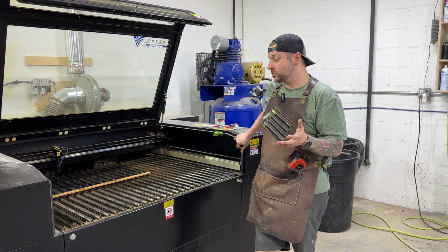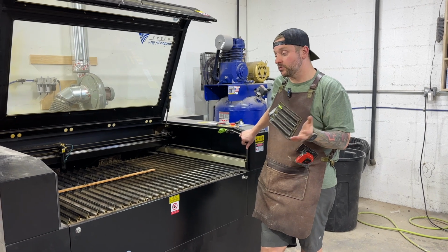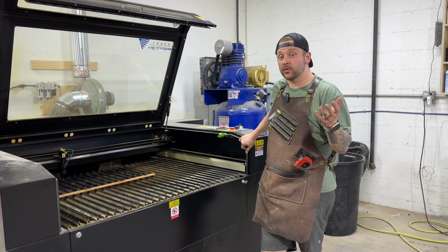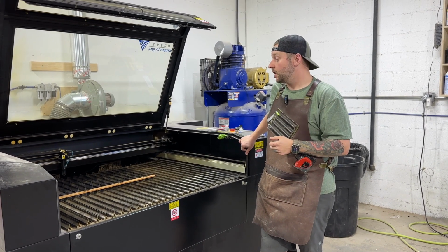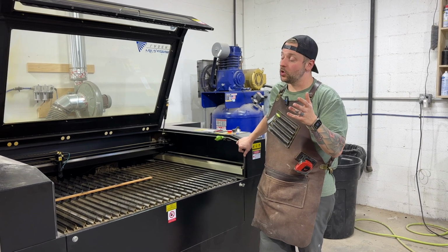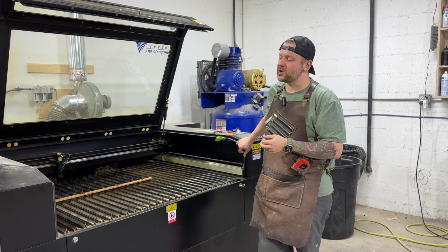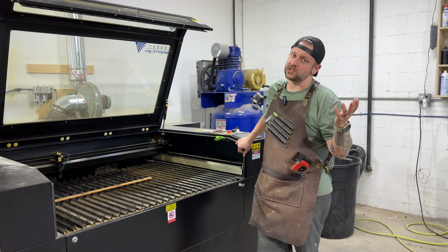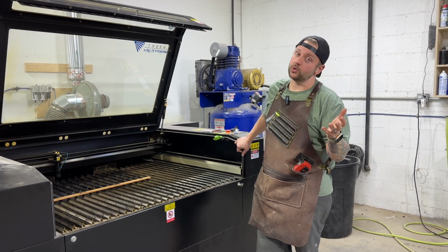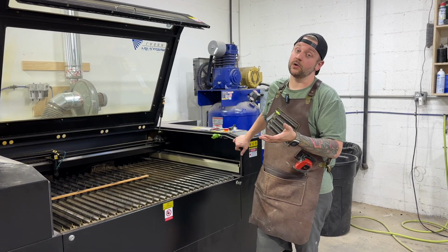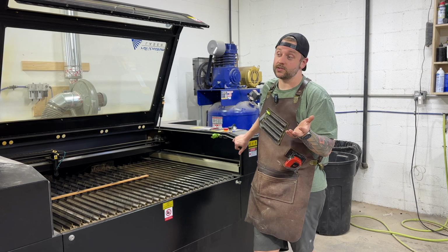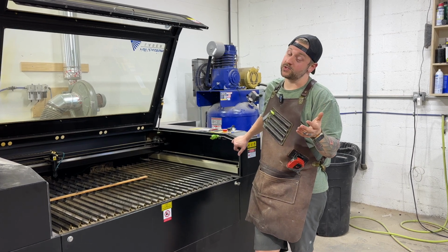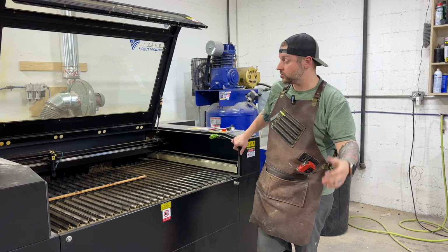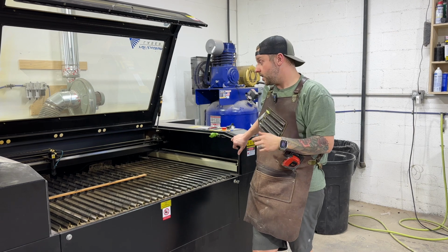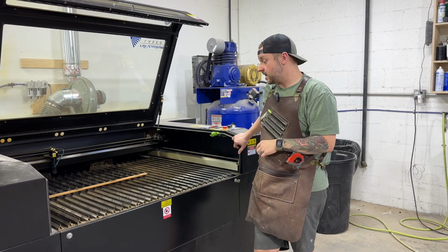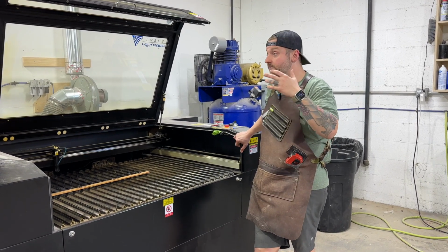They didn't offer any other solutions. Basically they said if you replace it with a third-party tube, you're going to void your warranty. They also told me the machine is coming up on a year, and that the tubes only last a year anyway, which isn't true. These tubes are all rated for 10,000 hours, and 10,000 hours running 24 hours a day is about 400 days. This machine runs nowhere near that, well under 10,000 hours, likely under 4,000 hours.